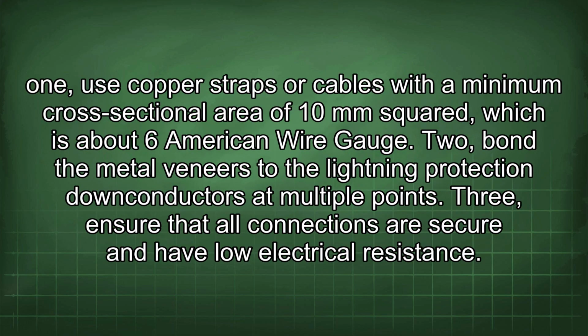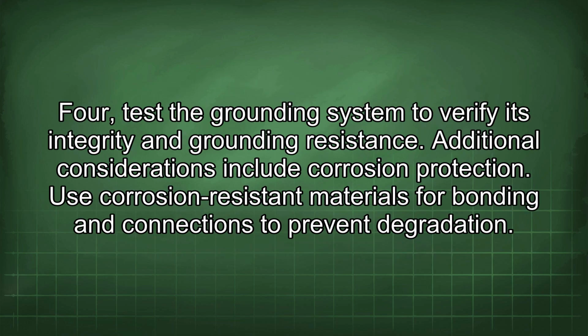1. Use copper straps or cables with a minimum cross-sectional area of 10 mm², which is about 6 American wire gauge. 2. Bond the metal veneers to the lightning protection down conductors at multiple points. 3. Ensure that all connections are secure and have low electrical resistance. 4. Test the grounding system to verify its integrity and grounding resistance.